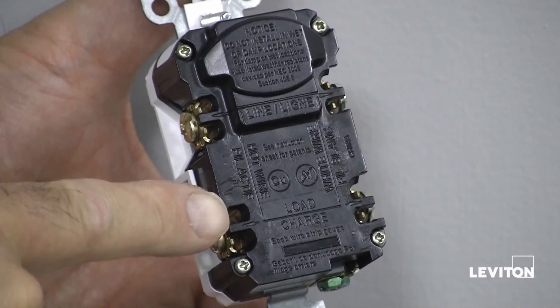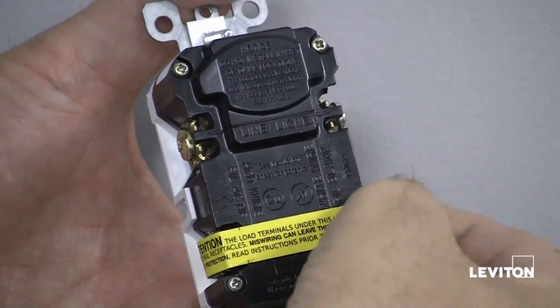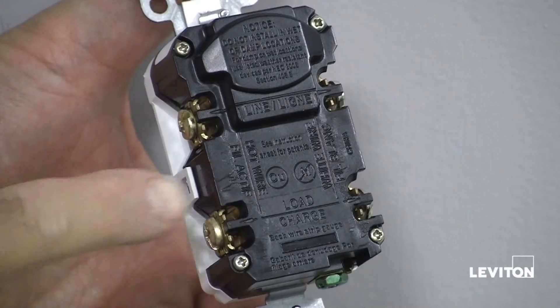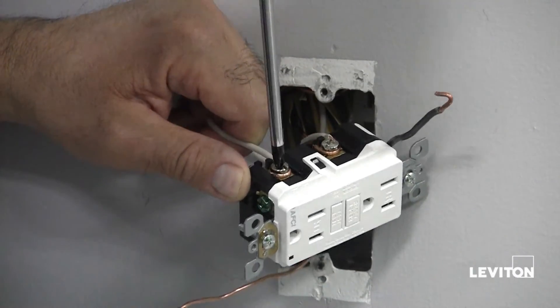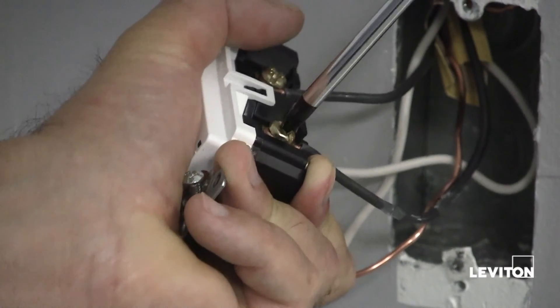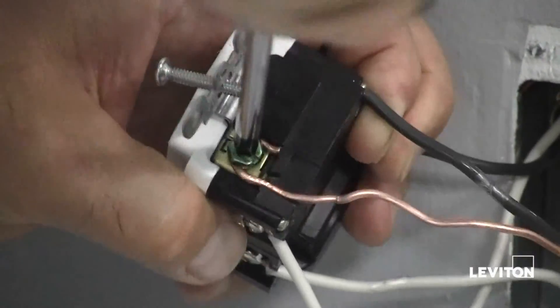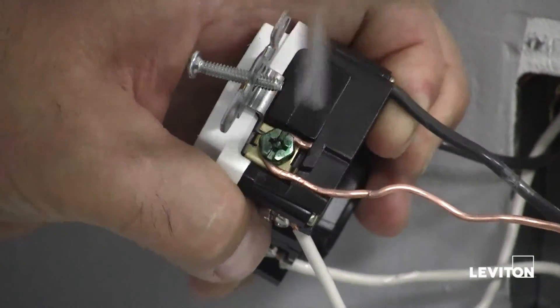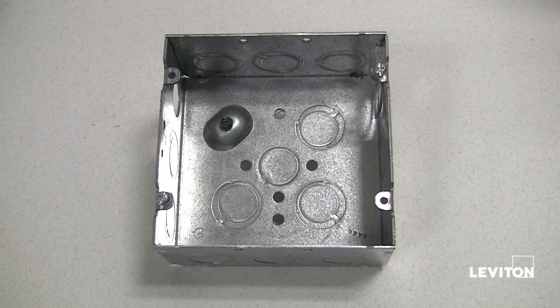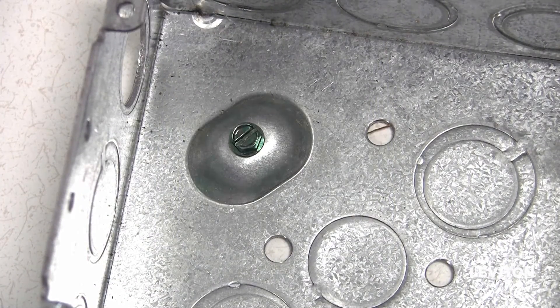Now let's connect the load wires to the load terminals. First, remove the yellow sticker to reveal the load terminals. The white wire connects to the silver colored terminal. The black wire connects to the brass colored terminal. Next, connect the green or bare copper wire to the grounding terminal on the GFCI. If your box has a grounding terminal, also connect a similar wire to the grounding terminal on the box.